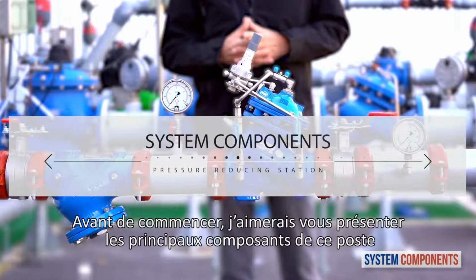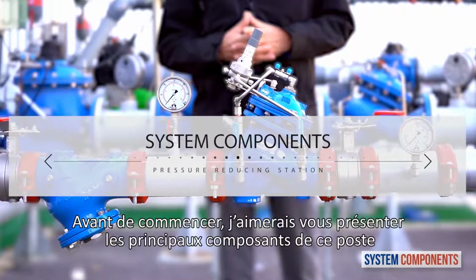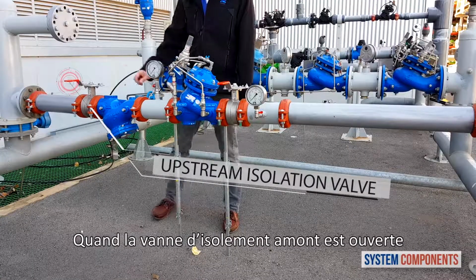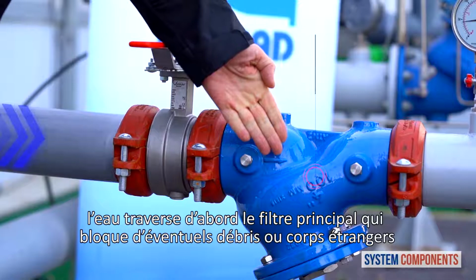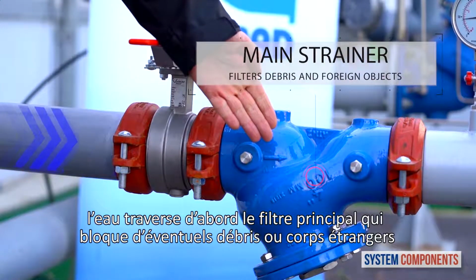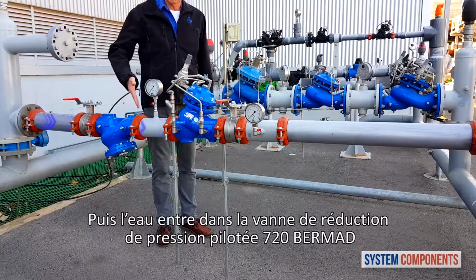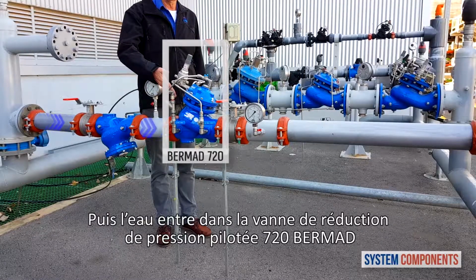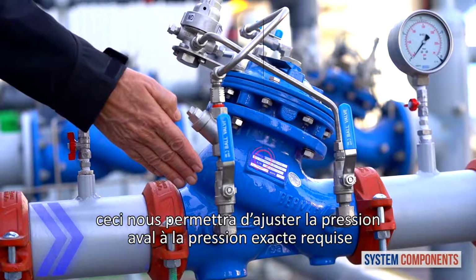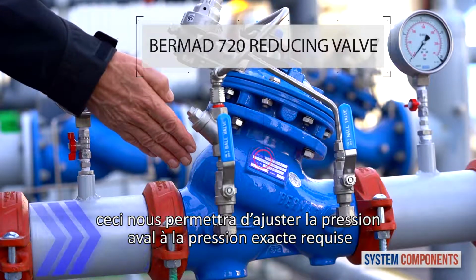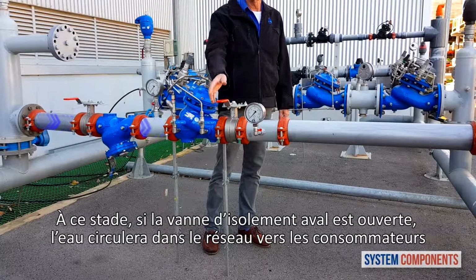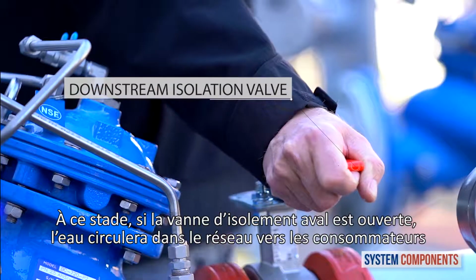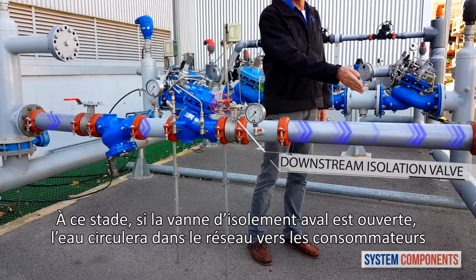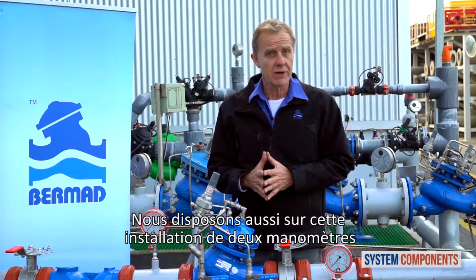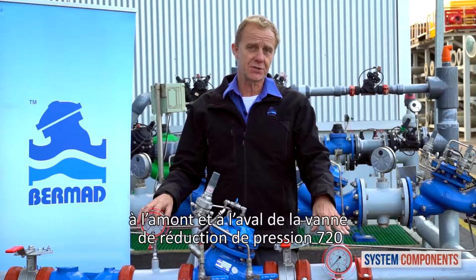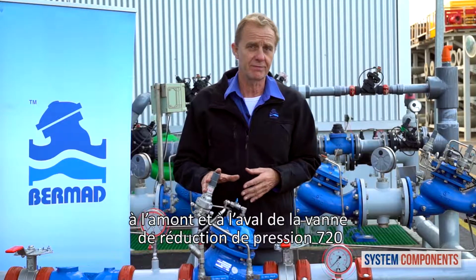Before we begin, I'd like to present the major components of this station. When the upstream isolation valve is open, water first encounters the main strainer, trapping any debris or foreign objects. The water then enters the BERMAD 720 pilot-operated reducing valve that allows us to adjust the downstream pressure to the exact pressure requirement. At this point, if the downstream isolation valve is open, the water will go on to the consumer. Also in this installation, we have two pressure gauges, upstream and downstream of the 720 pressure reducing valve.